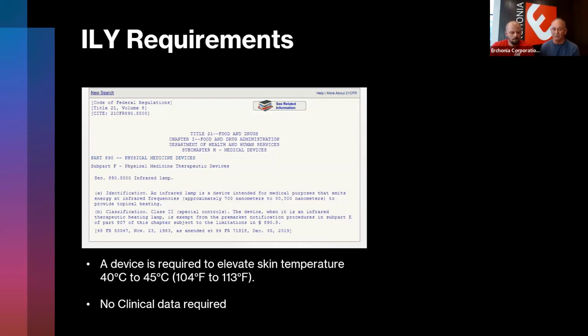Perfect. And as part of the category, which is the regulation of CFR 890, a device must elevate the skin temperature to 40 to 45 degrees Celsius, which is 104 to 113 degrees Fahrenheit, for an acceptable amount of therapeutic time, which is typically 5 to 10 minutes. When you increase the power, the watts of your laser, all you're doing is shortening the time it takes to heat the skin.